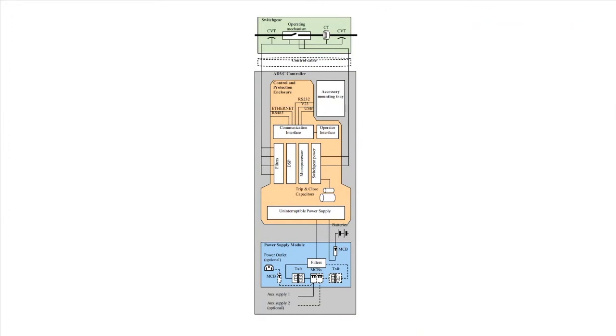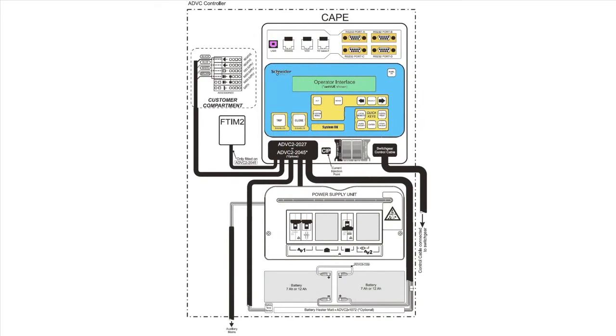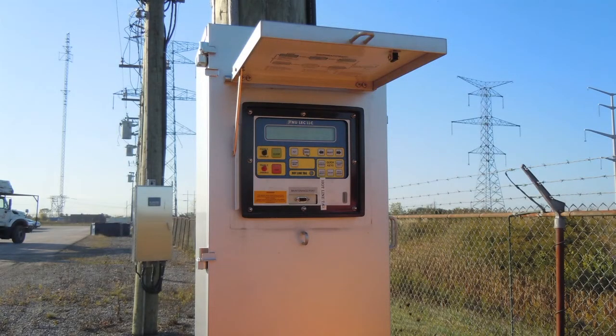The ADVC can be remote controlled via modems or other communications devices, controlled using a laptop computer connected directly via serial or USB connections to the ADVC, or by the operator interface. The operator interface offers full functionality to change settings, trip and close the switchgear, or display current values or past events related to the switchgear's function. The operator interface is mounted on the CAPE inside the ADVC controller and accessed by opening the cubicle door. It consists of a liquid crystal display and keypad and light-emitting diodes. Together, these hardware features provide a user interface to monitor and control the ACR.